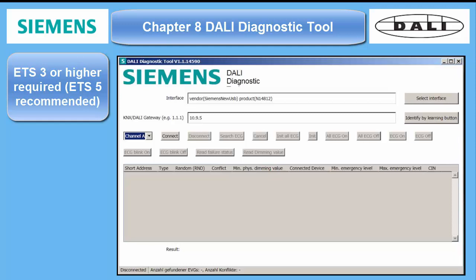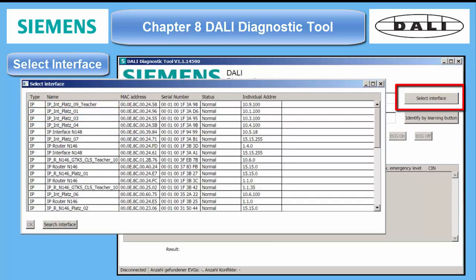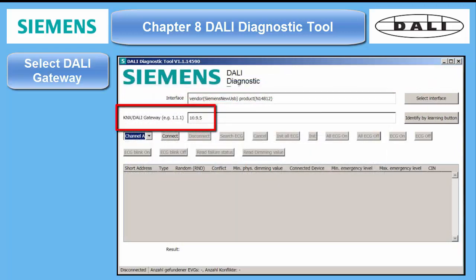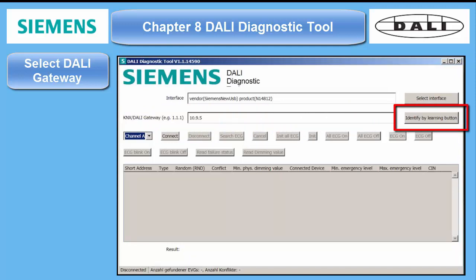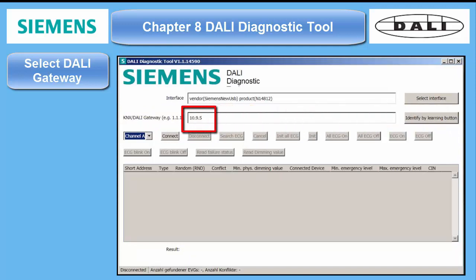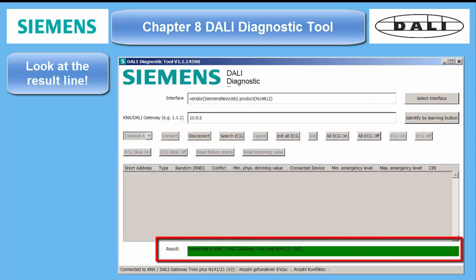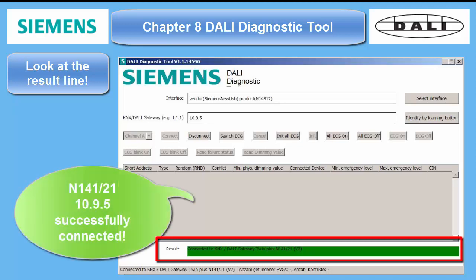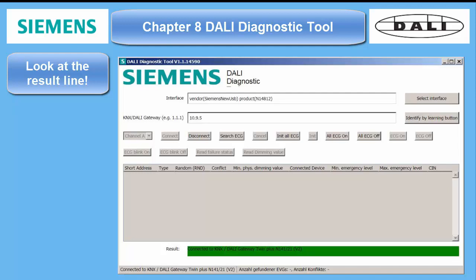The workflow to establish communication with the DALI bus is simple. First you select one of the interfaces, which you can see when you press the button Select Interface. The next step is the selection of the corresponding DALI gateway. If its KNX physical address is unknown, it can also be retrieved through the well-known procedure by pressing the device's program button. Otherwise you enter the physical address right here. Note the result line — it will always tell you what the tool has done before. I will connect the DALI gateway twin plus with the address 10.9.5 now. Successful.